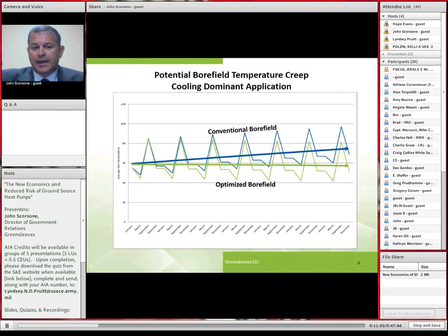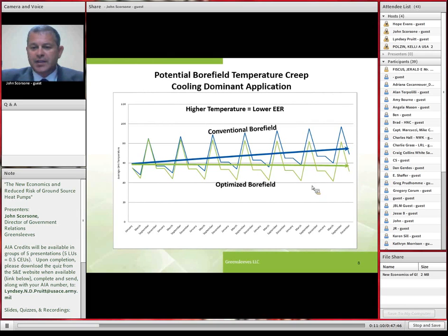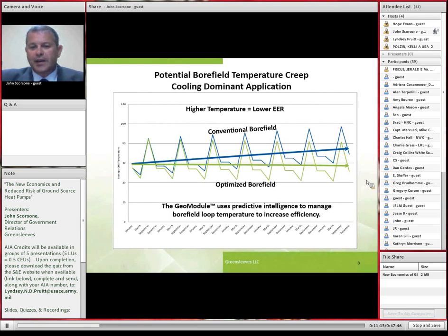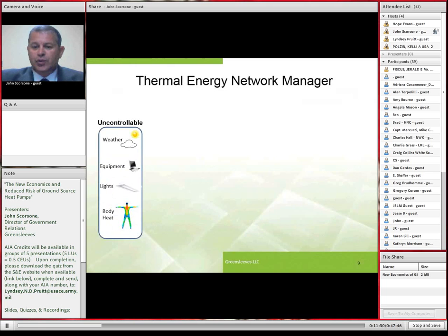So the bottom line here is the GeoModule using predictive intelligence to manage the bore field loop temperature to increase its overall efficiency. That's the value of intelligent predictive algorithms. But let's just look at this another way. The world is full of uncontrollable variables. The weather, the plug load, lighting that turns on and off, the number of people that go in and out of our building. Those inputs are uncontrollable, and a traditional HVAC system is just merely reactionary to what happens.